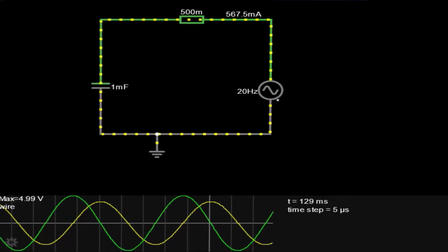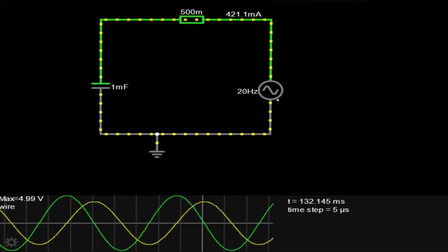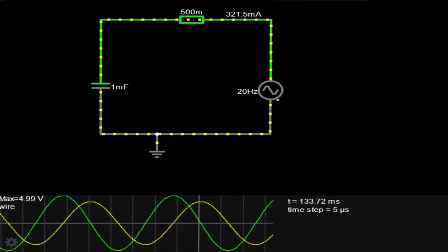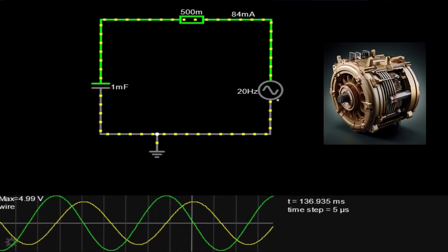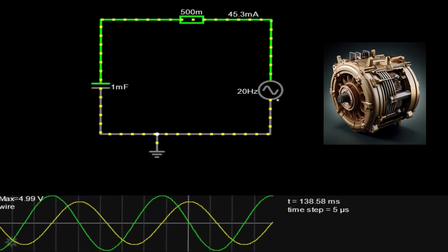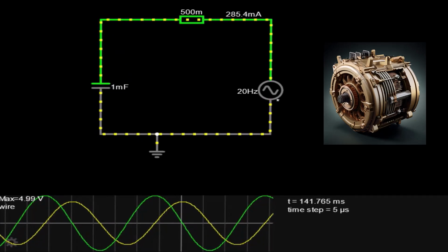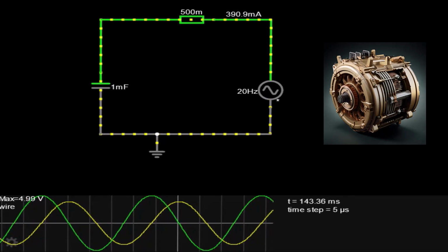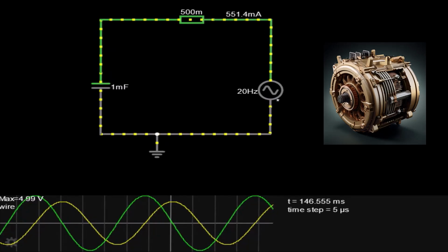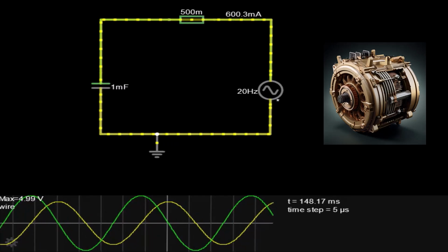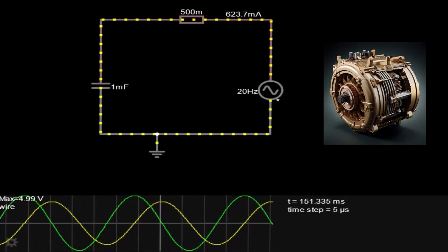So this is actually a very handy trick. For example, if you have a single-phase electric motor, you can have two coils inside of the motor. If you put voltage on these coils, they would activate at the same time, but by adding one capacitor in series with one coil, you will see this coil goes a little bit faster than the other coil, and this way we can determine the direction in which the motor has to start. So if the motor is not starting, it can be either the startup coil or the capacitor that fails.